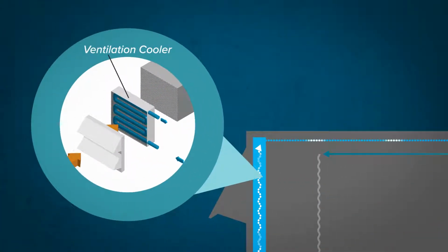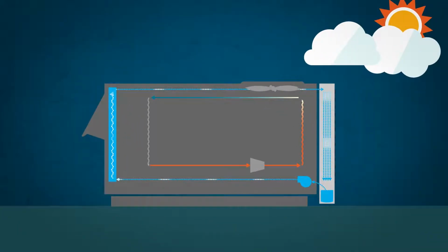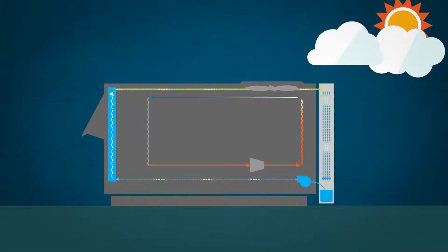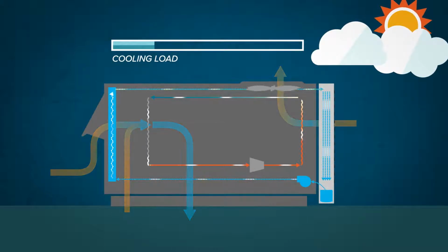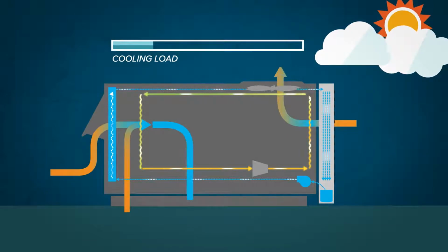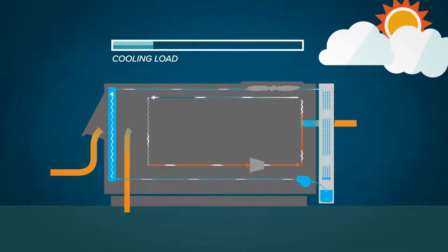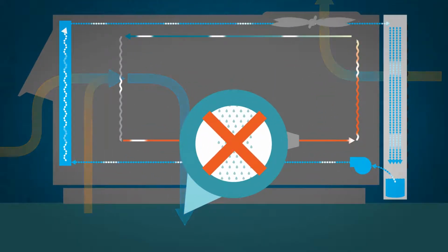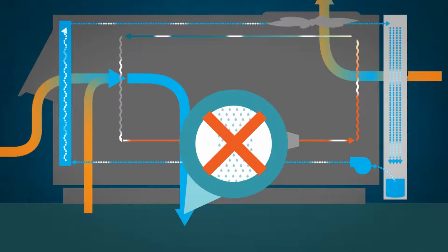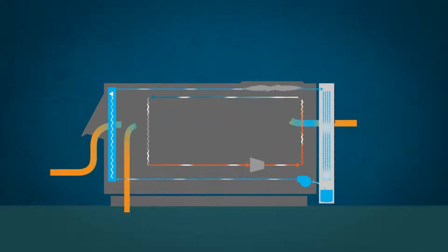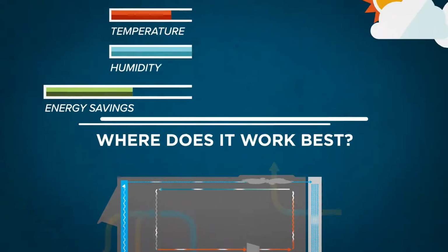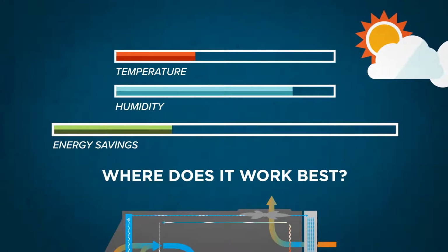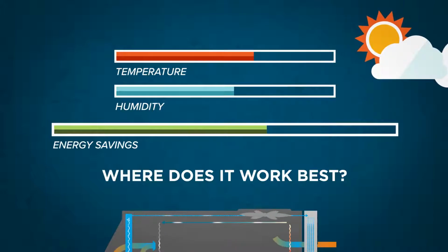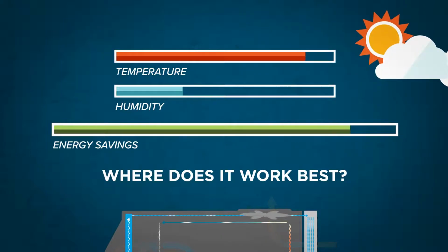This water circulates through a water-to-air heat exchanger, located in the ventilation airstream, which cools ventilation air before it enters the rooftop unit. The water is then returned to the evaporative media on the condenser side of the DualCool. In this way, DualCool simultaneously reduces the cooling load and improves the efficiency of the vapor compression cycle. Although evaporation is used to provide these benefits, no humidity is added to the air that then enters the building. The evaporated water is rejected outdoors by the condenser fan. DualCool is effective for a range of climates and applications, but the energy savings achieved increases as outdoor temperature increases and humidity decreases. So, DualCool is particularly well suited for hot, dry climates.